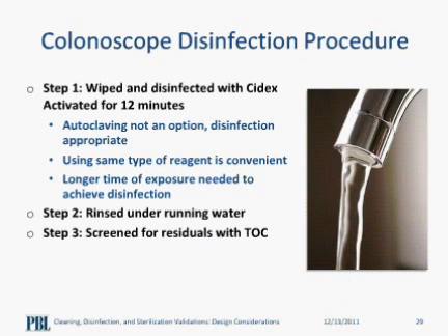And how do we know it is acceptable? We have to perform TOC testing to screen the device and ensure that any organic residuals are within acceptable limits. Alternatively, we can also do screening tests such as analytical testing or quantitative analysis. Proper cleaning and disinfection and adequate rinsing will surely render a medical device safe for reuse. If in the evaluation it passes all the acceptance criteria, then the process is validated. That is all I have for this case.